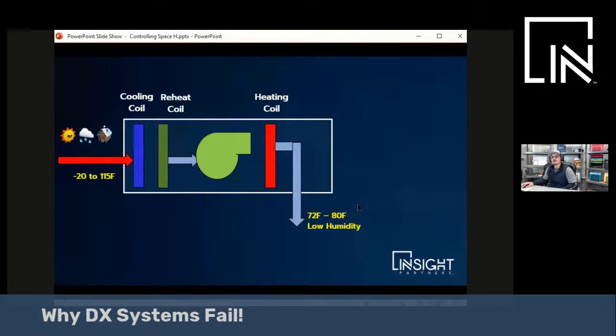What do you need in your unit at a minimum to make this happen? What you need is a modulating digital or VFD compressor, modulating reheat, modulating is the keyword there, and modulating heat.